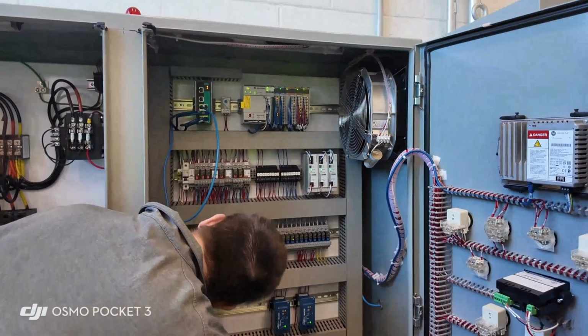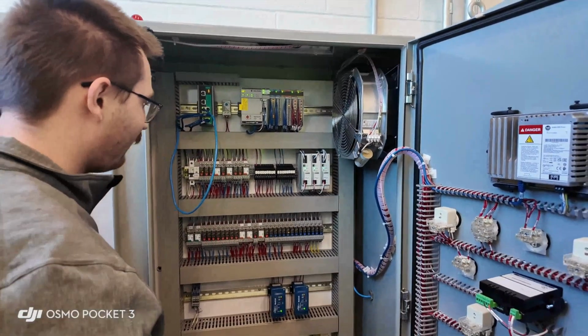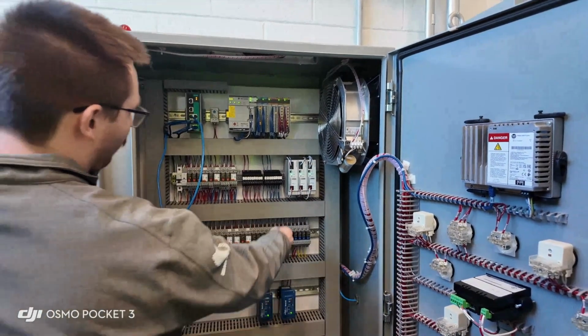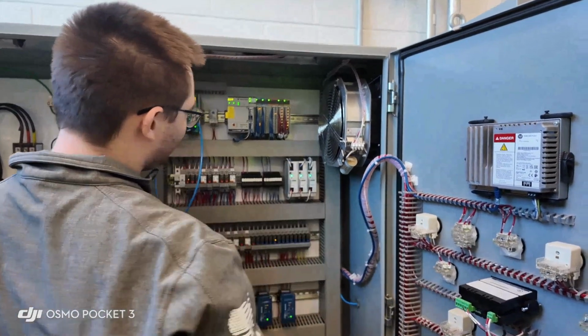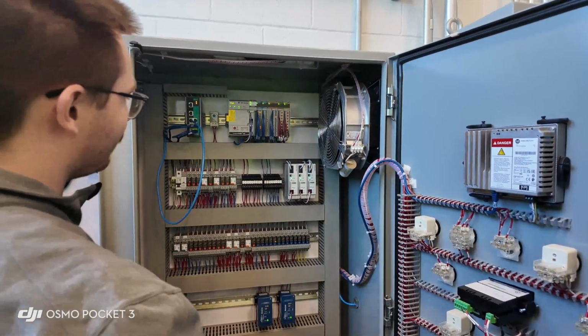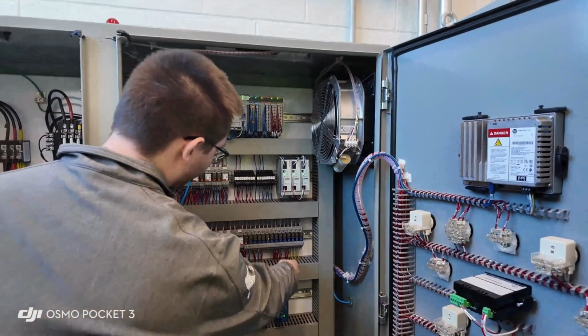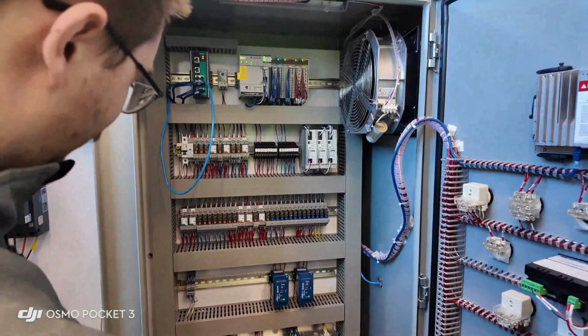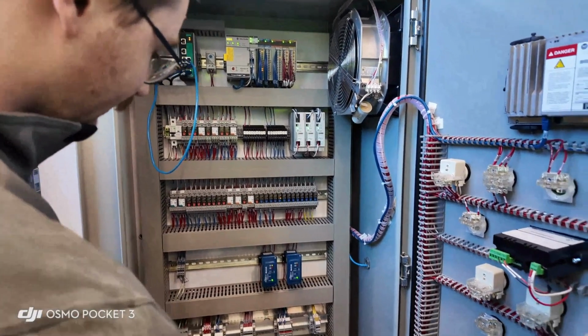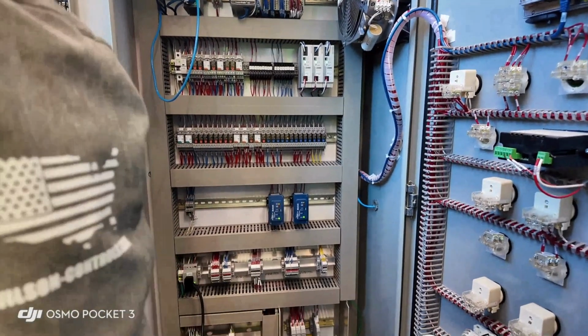What's the teal? This is the 24 volt. And wire codes: the red's 120, white's the neutral for 120, the white with the blue stripe is the PS minus. Yellow means it's unknown voltage coming from a foreign source. The green with the yellow stripe is ground. And then we have twisted shielded pair for analog signals.